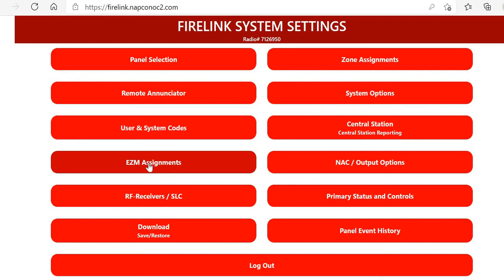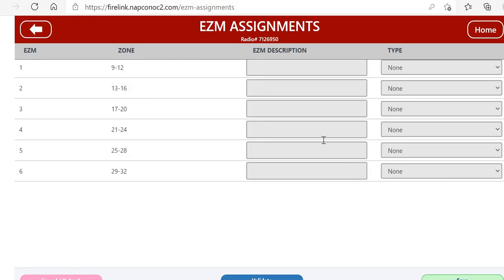But we can use EZMs or GEM-C EZMs for non-powered fire devices like water flow, gate valves, pulsations, mechanical heat detectors, any kind of other auxiliary monitoring like a fire pump for pump run or pump fail. If you had a generator, any type of Ansul system, any type of those applications.